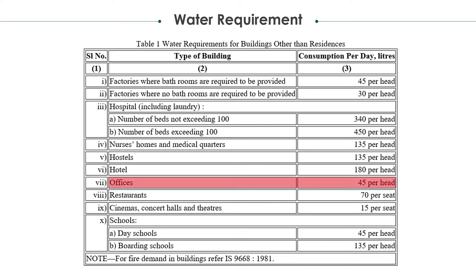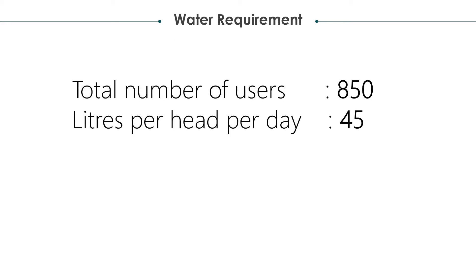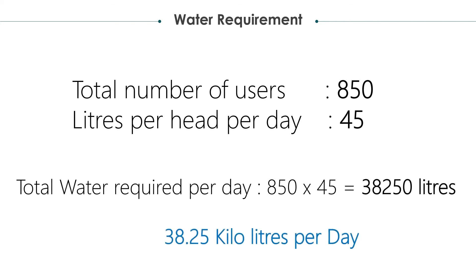For every office building, 45 liters of water is required per head per day. Total number of users are 850 members. Liters per head per day to be allocated is 45 liters. Multiplying both, we get 38,250 liters per day, which is 38.25 kiloliters per day.